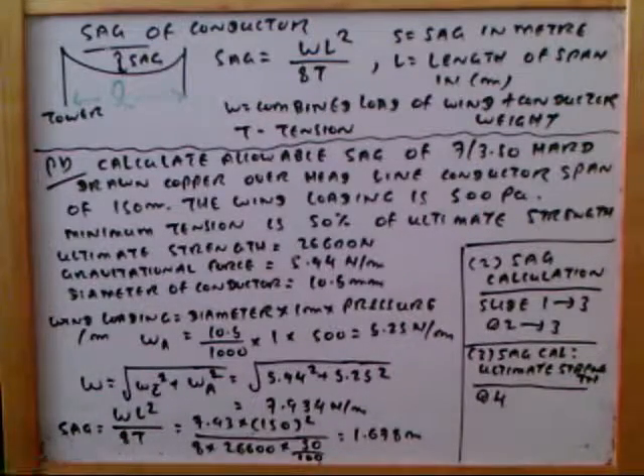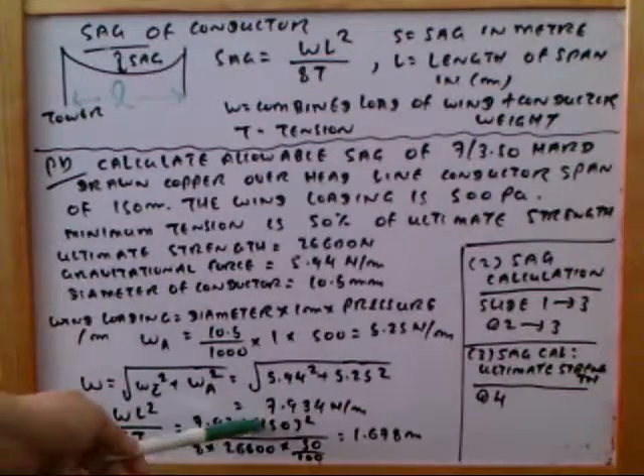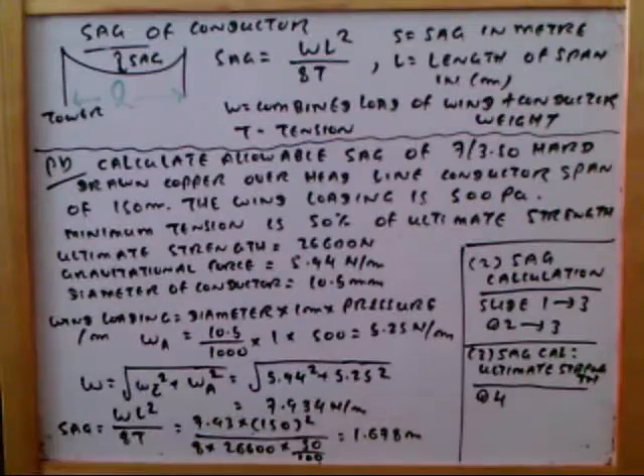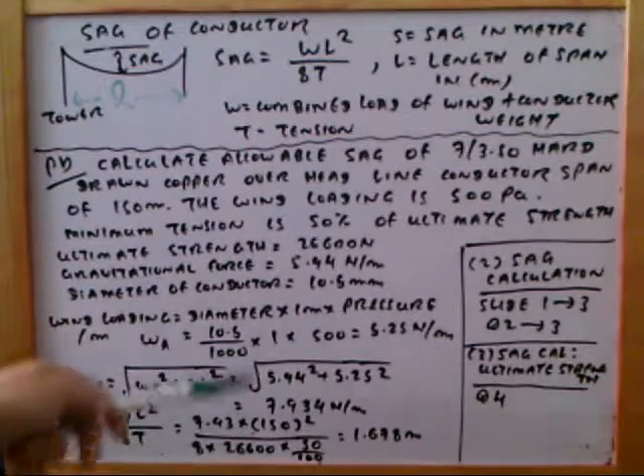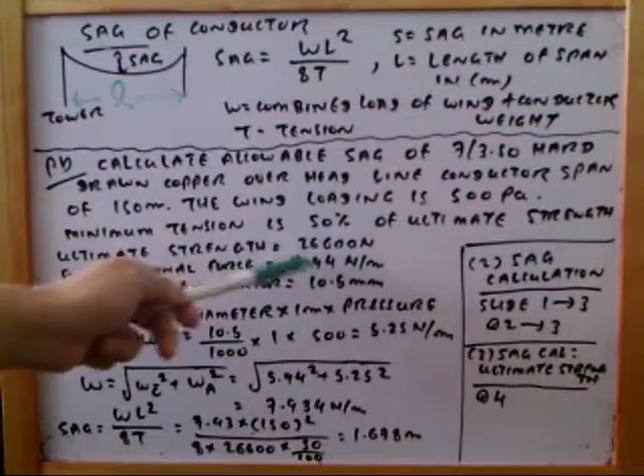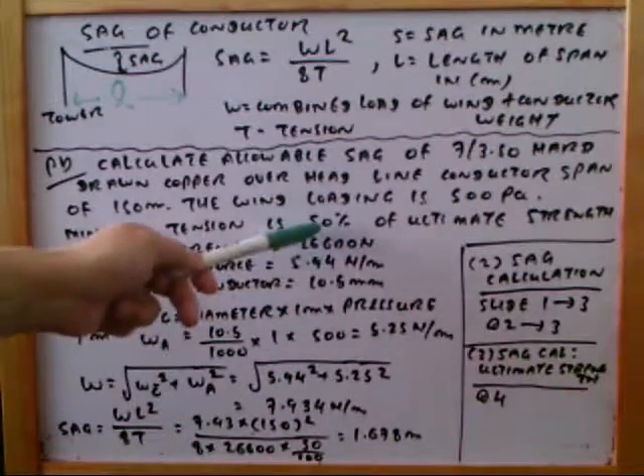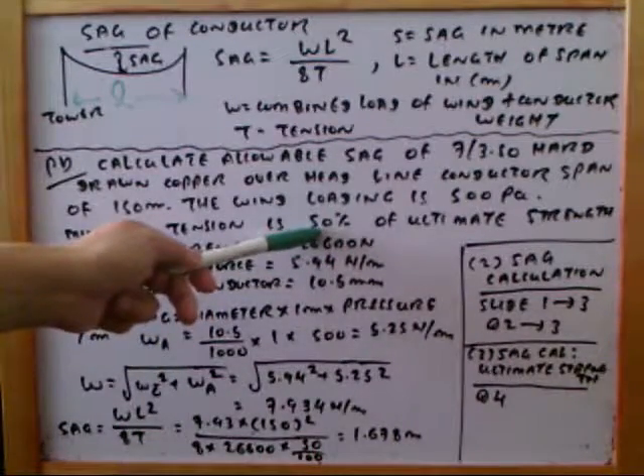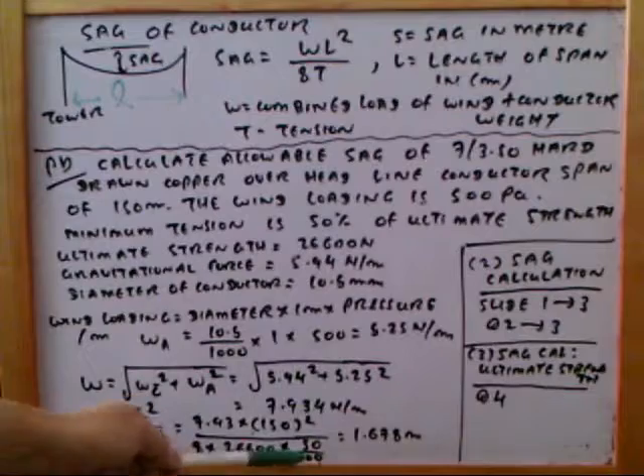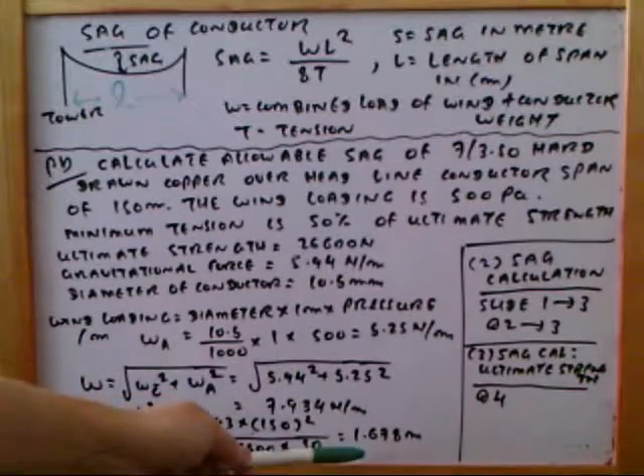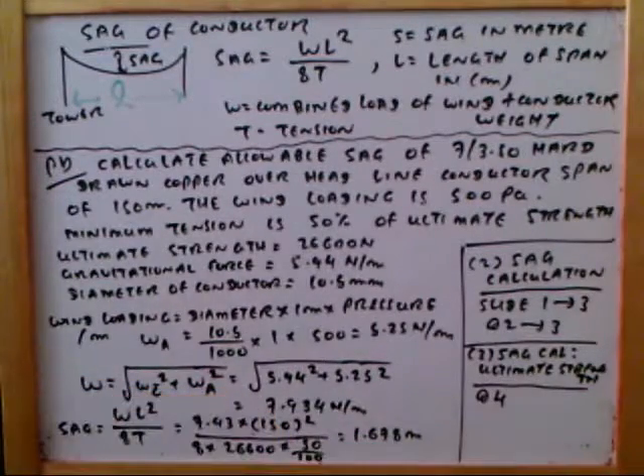We can now calculate the sag: sag = wl²/8T = 7.934 × 150² / 8T. The tension T is 50% of the UTS of 26,600 newtons, so T = 26,600 × 50/100 = 13,300 N. Solving this, the sag equals 1.698 meters.